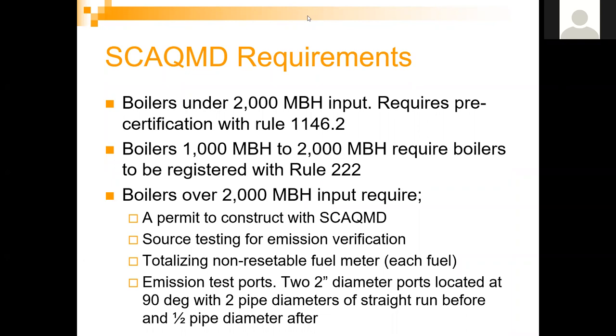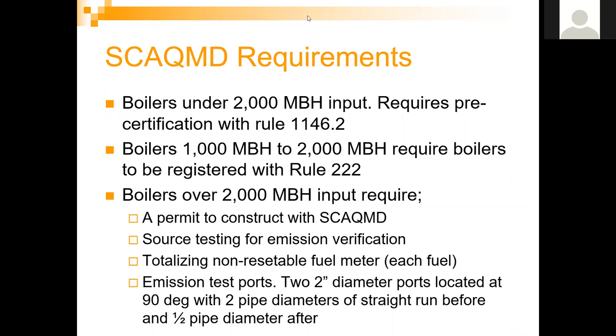Addressing some questions: for Rule 222, the fees are not annual — they're a one-time registration fee for boilers between one million and two million BTUs per hour input. Also, the 2,000 MBH pre-certification applies to both boilers and water heaters — including boiler-type and even tank-type water heaters under 2,000 MBH. Those need to be pre-certified with the local air district as well. This applies to boilers used in water heating applications, not only gas-fired boilers.